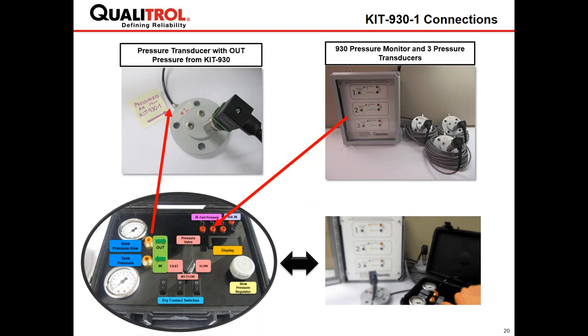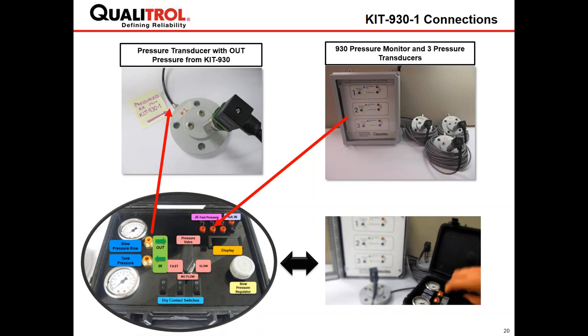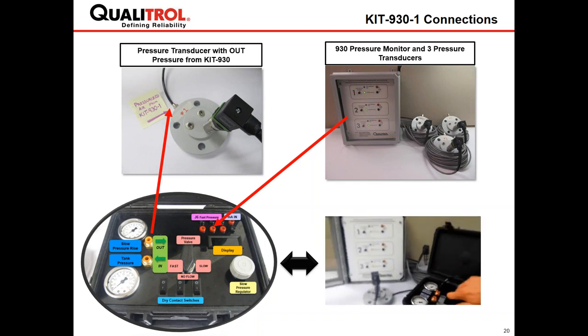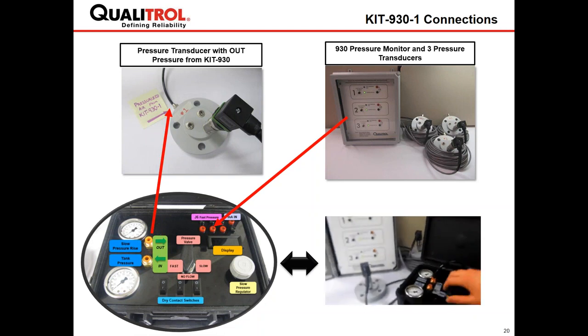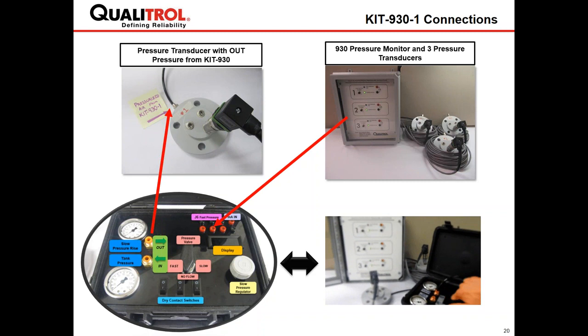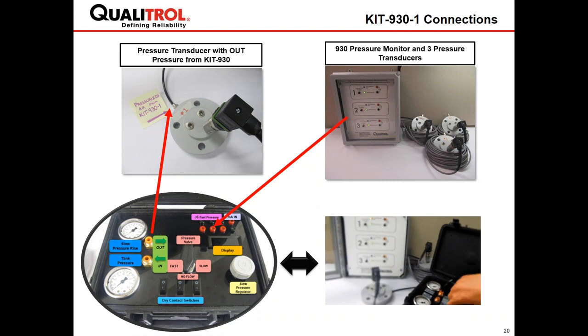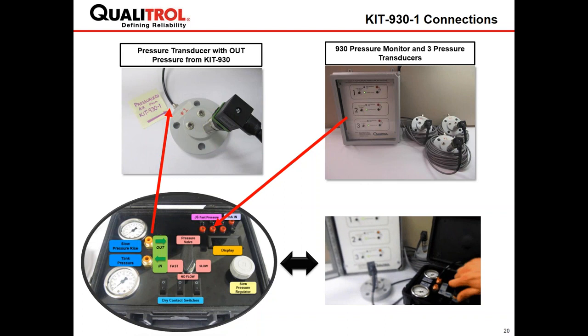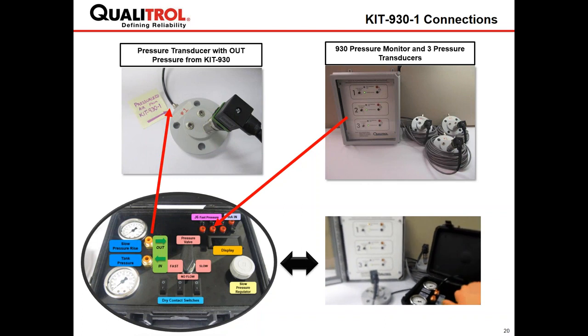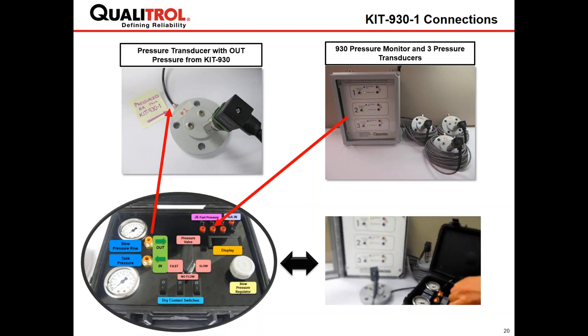If we concentrate on the bottom left-hand corner, the center of the kit, there is a pressure valve. Turning that valve to the fast or slow position, as we see on the video to the right, indicates a change of pressure, whether it was a fast pressure or a slow pressure, and the LED then changes light on the monitor itself.